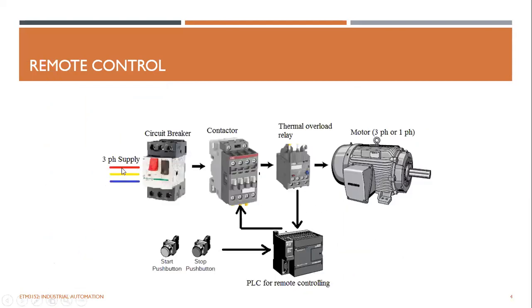And for the remote control, we have three-phase supply, and all the control is done remotely, which means from a distance, by a PLC. Three-phase supply is fed to a circuit breaker, and then the contactor. So the contactor is controlled by the control signals of the output port of a PLC. And the start and stop buttons could be located remotely, close to the PLC or any other control cabinet.